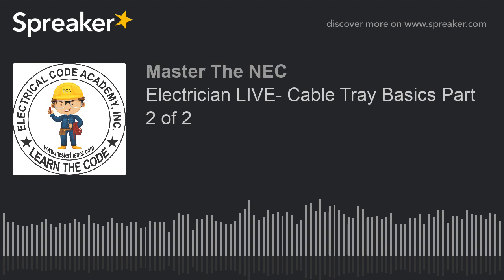This one is dealing with a continuously covered cable tray. So it's got a cover on it. And here's what it says. Let me read it. It says B: where cable trays are continuously covered for more than 6 feet with solid unventilated covers, not over 95% of the ampacity of Table 310.16 or 310.18, if we're dealing with the 40°C application, shall be permitted for multi-conductor cables.